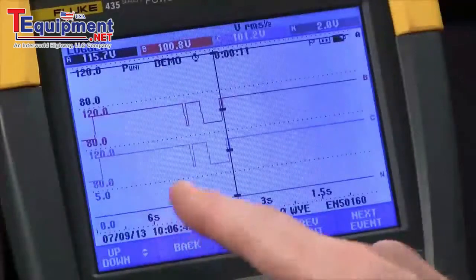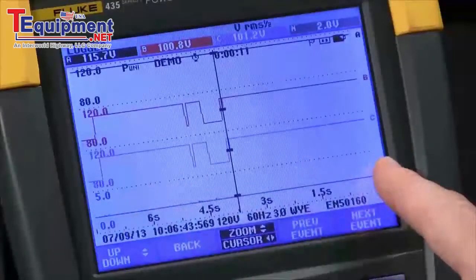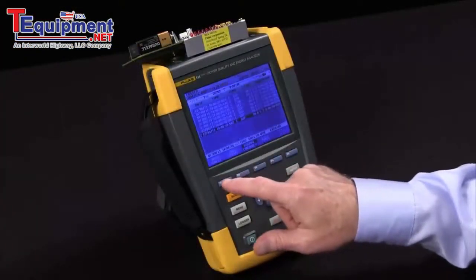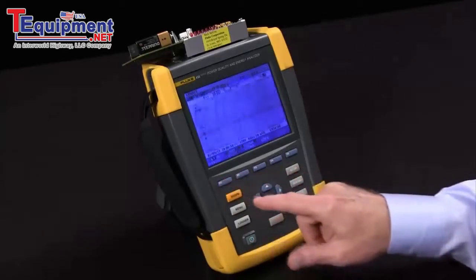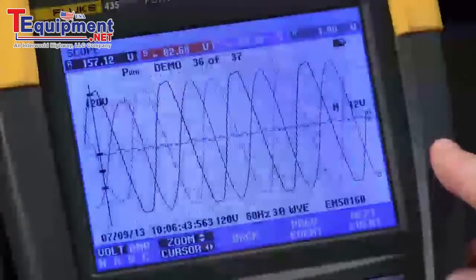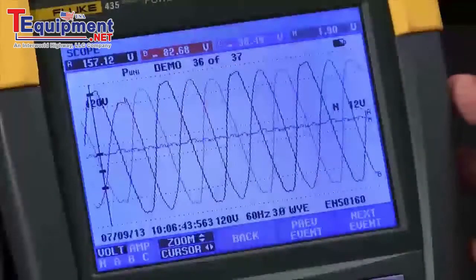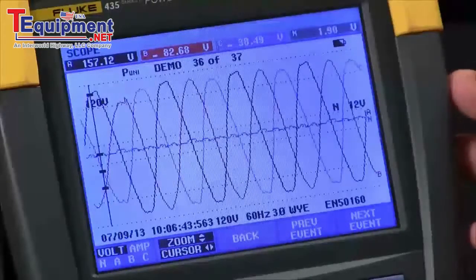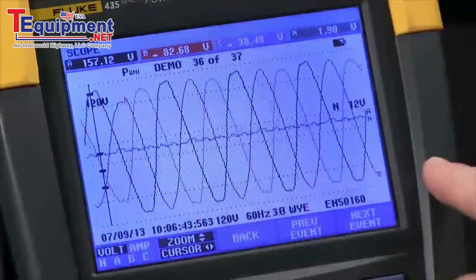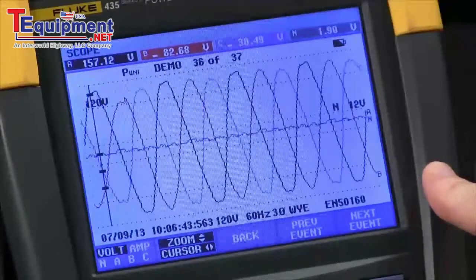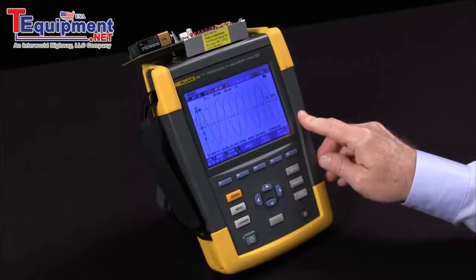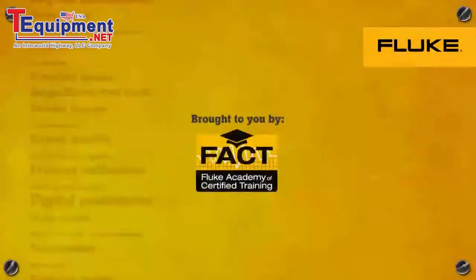The RMS trend allows me to see the actual trend that happened over time, and the wave event captures the waveform. The key here is that even with a 10-second recording interval, I still don't miss any detailed changes as far as events that occurred. And that's how you use the logger function on the Fluke 435.